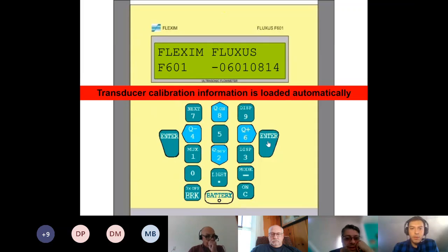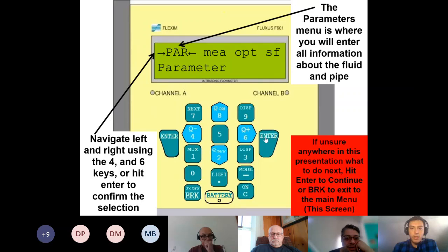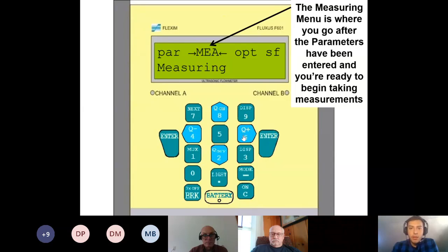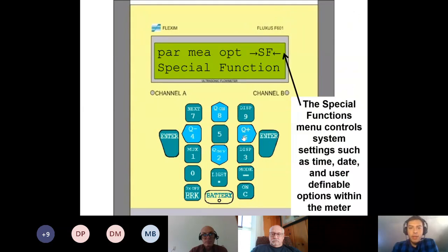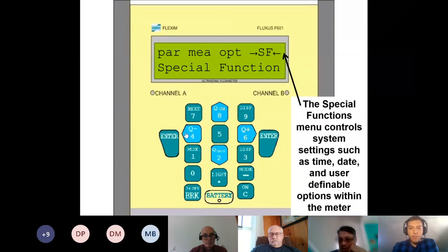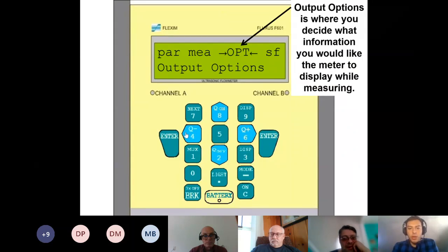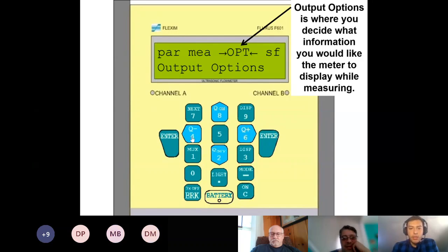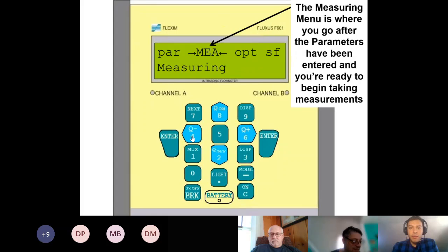There it is right there. It's telling you your serial number, and this is the main menu of the Flexim that should look very familiar to you folks. The four main menus: parameters, measurement, output options, and special functions. Special functions, you can change your dates, times, settings. Output options is where you would change your output, your 4 to 20. You can change your units here. Basically, you can determine what you'd like the meter to display.